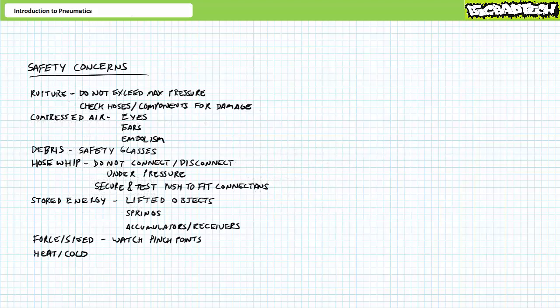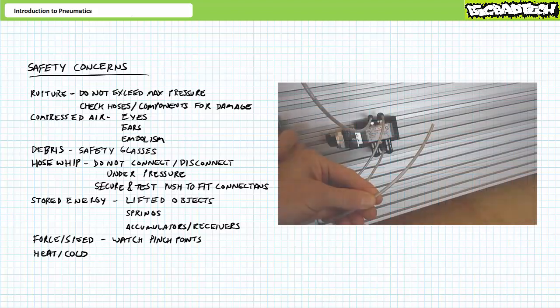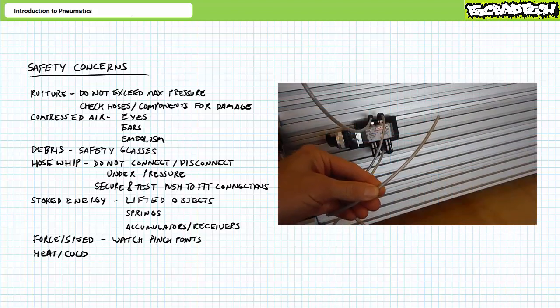Lastly, let's quickly review some safety concerns unique to fluid power systems. As you're now aware, the fluid filling a fluid power system is under pressure. Hoses and containers can catastrophically rupture if pressure exceeds permitted maximums, or if the hose or container is damaged. Even if something doesn't explode, compressed air itself can blind or deafen an individual if struck in the eyes or ears. Additionally, compressed air injection into the skin can cause an embolism. Escaping air can blow a veritable storm of sharp, dirty debris in your eyes and lungs.